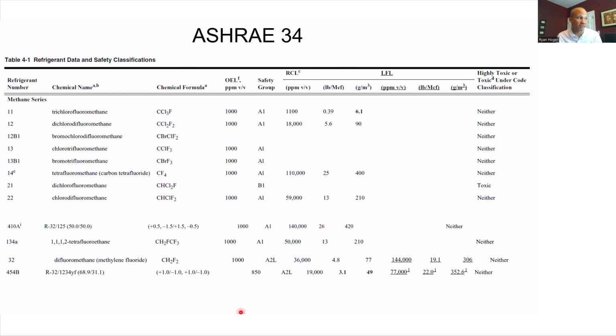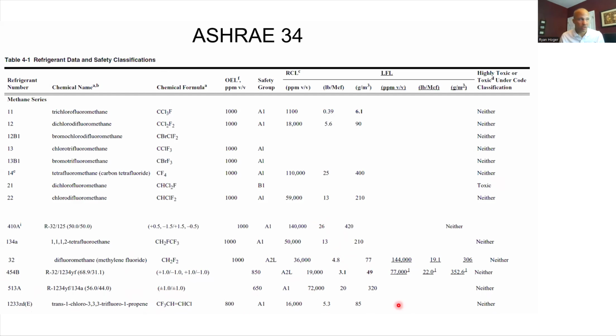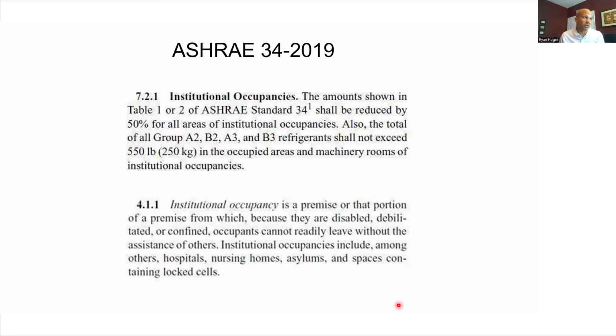And obviously there's stuff in the flammable section as well. For some of you doing chillers, you probably know that we have not switched to A2Ls on most large chillers. They're still using A1s. So 513A, 515B, 1, 2, 3, 3Z, D, E. I can't even say it. Those are still A1, so nothing in the flammable section for those. So what do you do with this refrigerant concentration limit?